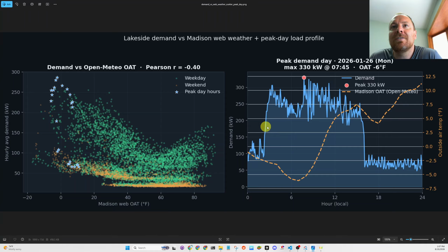So maybe the idea would be, this is what I want to see, if reinforcement learning can understand this. We should be able to model this too in EnergyPlus, that if the building was running 24/7 during this event, would the demand have stayed below 200 kW? Would they still be paying for this, which is a big chunk of change.